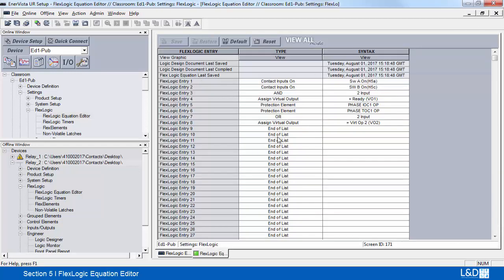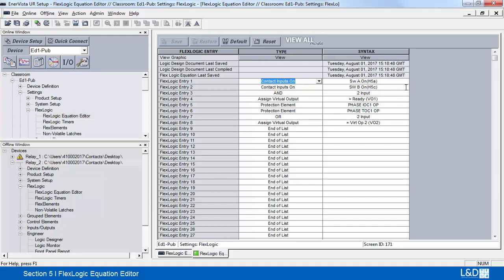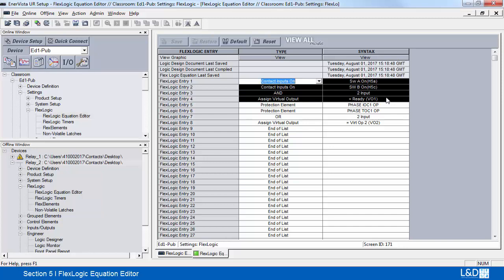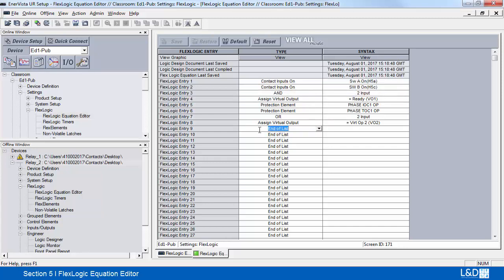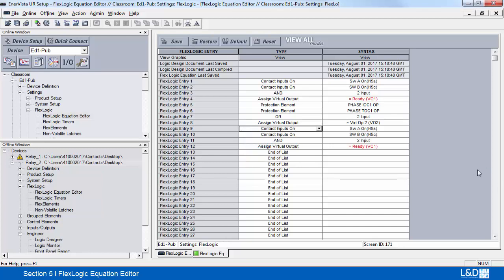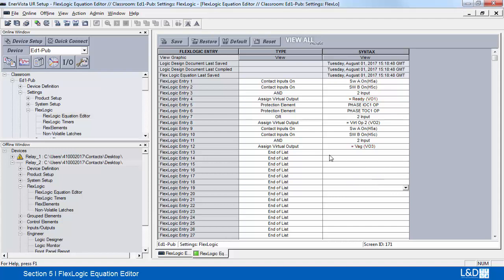If you make any changes here — when you right click, you can copy a circuit, you can paste, you can insert, you can also delete. So if I wanted to duplicate this circuit, I can hit Control C or do a copy, come down here and do paste. The only thing I have to do is make sure there's no duplication on the virtual output, so I'll make the necessary change. And then when I save it, this will be saved directly into the relay.